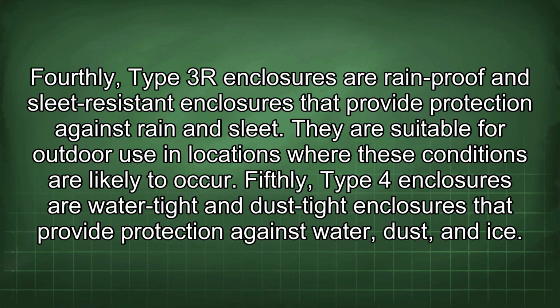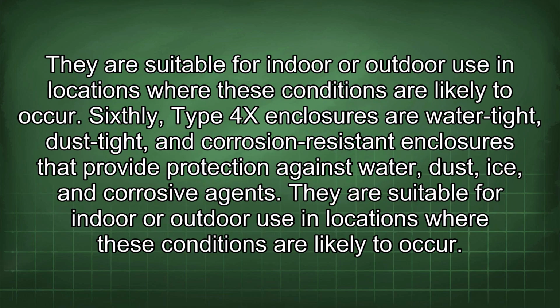Fifthly, Type 4 enclosures are watertight and dust-tight enclosures that provide protection against water, dust, and ice. They are suitable for indoor or outdoor use in locations where these conditions are likely to occur.